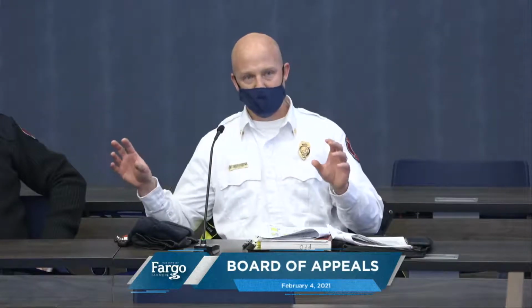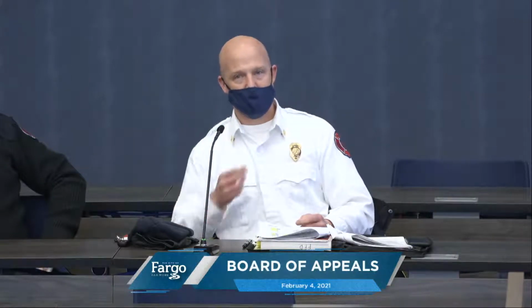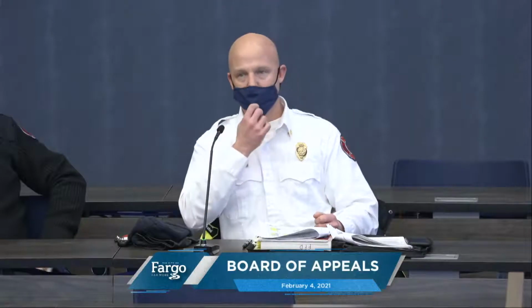On an open parking garage, when you think about fire department operations, the reason it's open is that there's a requirement for the percentage of open space on the sides, at a minimum on both sides of the building, to allow heat and smoke to escape. That allows our department to operate from a standpipe and a stairwell and pull hoses, and we're fighting it essentially the same way we would in a parking lot. The only difficulty is you could be 5+ stories in the air, so you have that extra time to get up there.